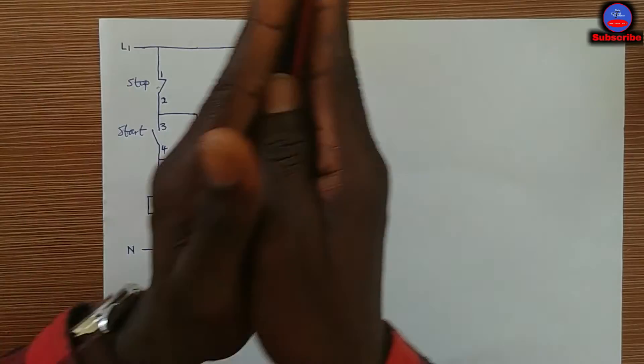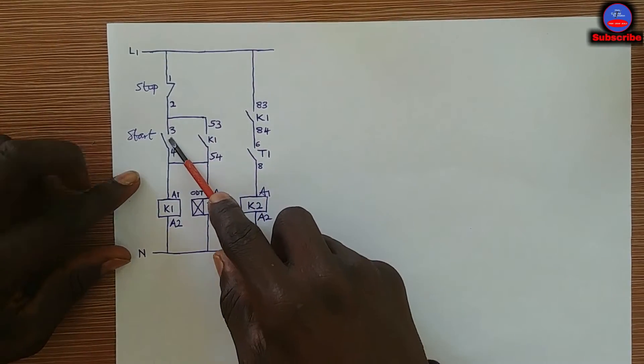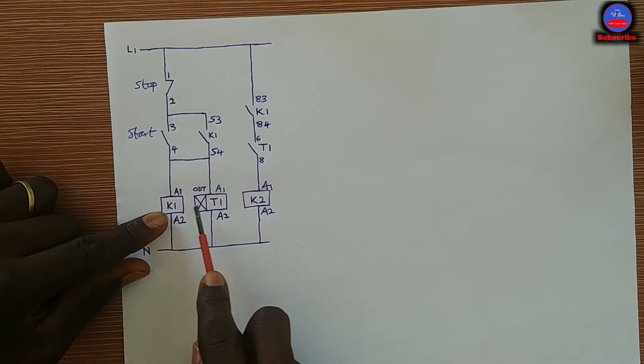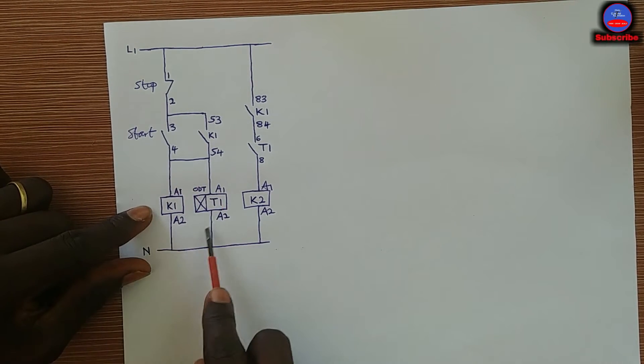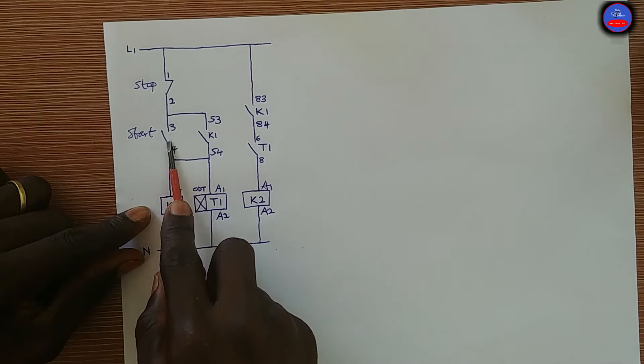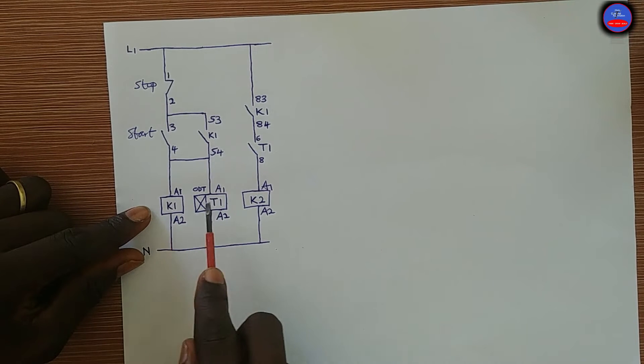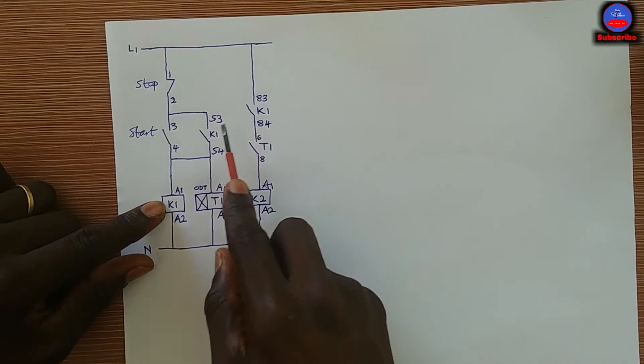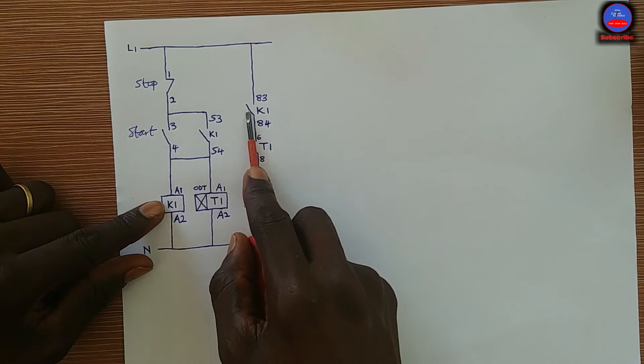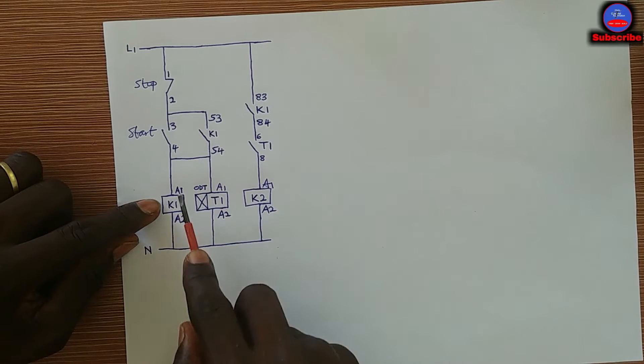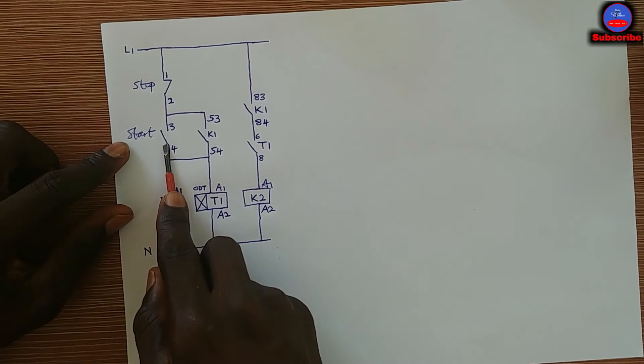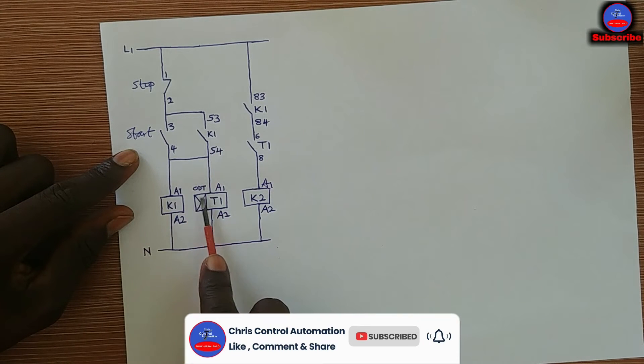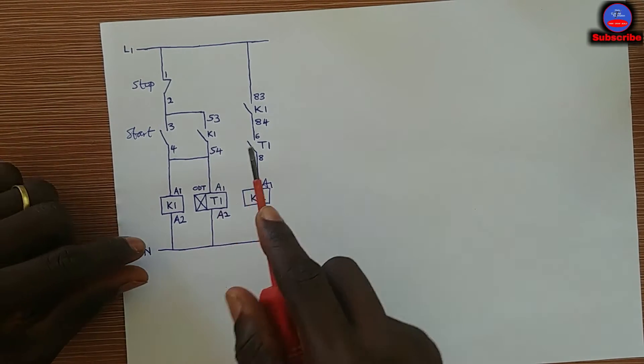Now let me explain the circuit in detail. When the start push button is pressed, K1 and T1 — Contactor 1 and the timer — both energize at the same time. The line closes and they both energize simultaneously. When K1 energizes, its contacts close, and this contact serves as a hold-on contact for K1, so that when I remove my hand, the contactor stays energized and keeps the current flowing.